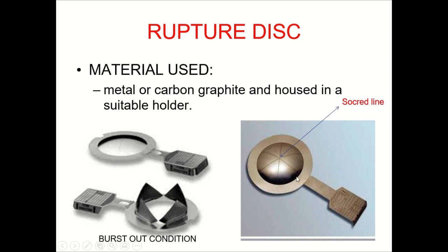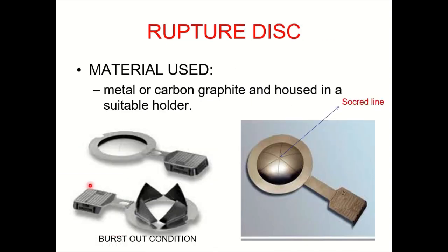This is one type of rupture disk which has scored lines. These scored lines pop open when the pressure exceeds the set limit. However, it will never close back to its original position — you have to replace the device once it has opened up.